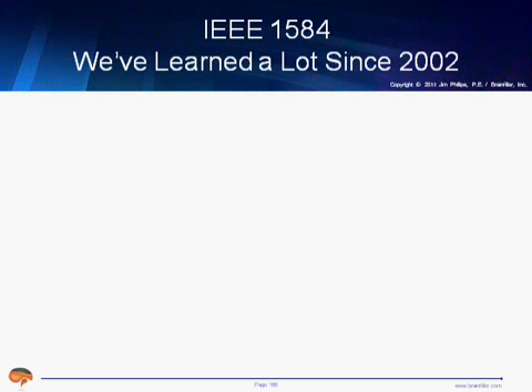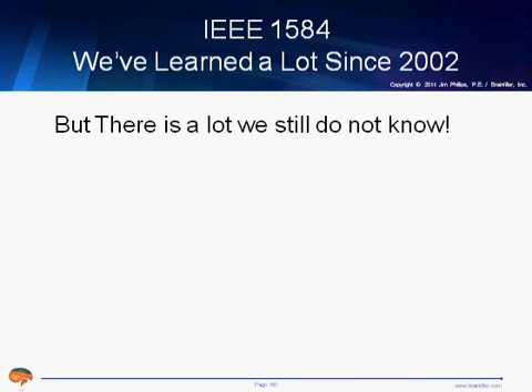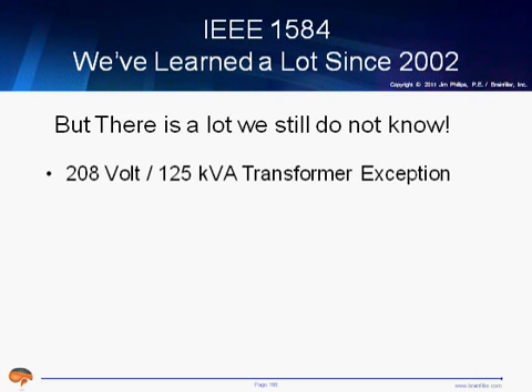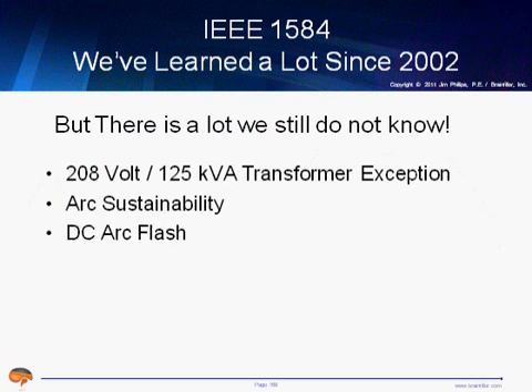And since the 1584 standard first came out, we have learned a lot. A lot of new things have happened. Some of the things that we have learned and that we're still working on: the 208-volt 125 kVA transformer exception, which I'm going to talk about in a little more detail. Arc sustainability is an issue that we recognize is significant, but it is still being investigated. DC arc flash, we're seeing some movement with DC arc flash within NFPA 70E. I'm going to talk a little bit more about this in a few moments.